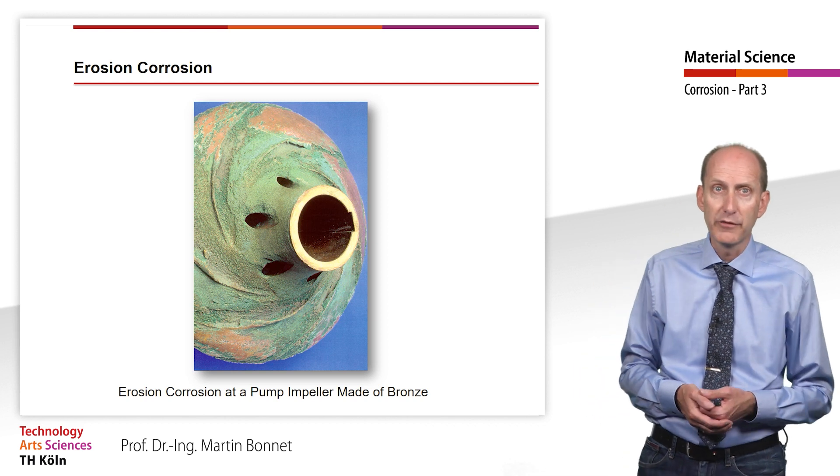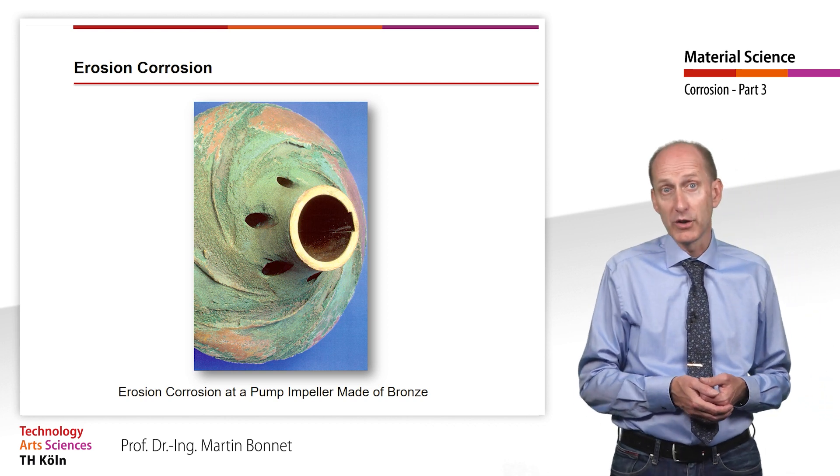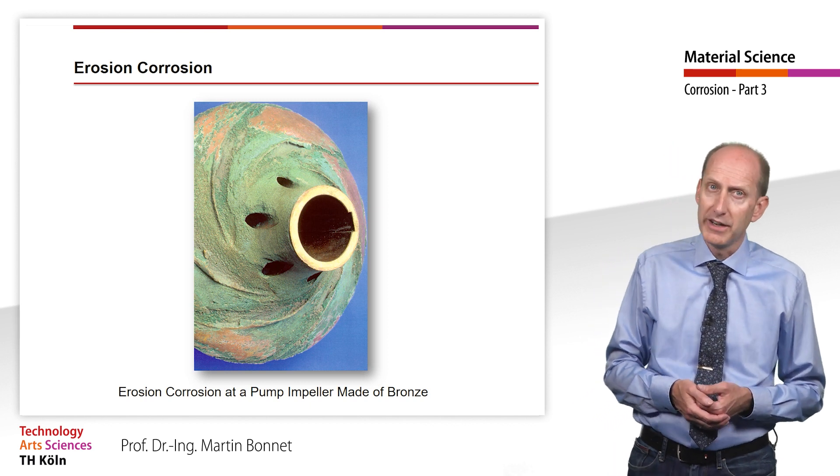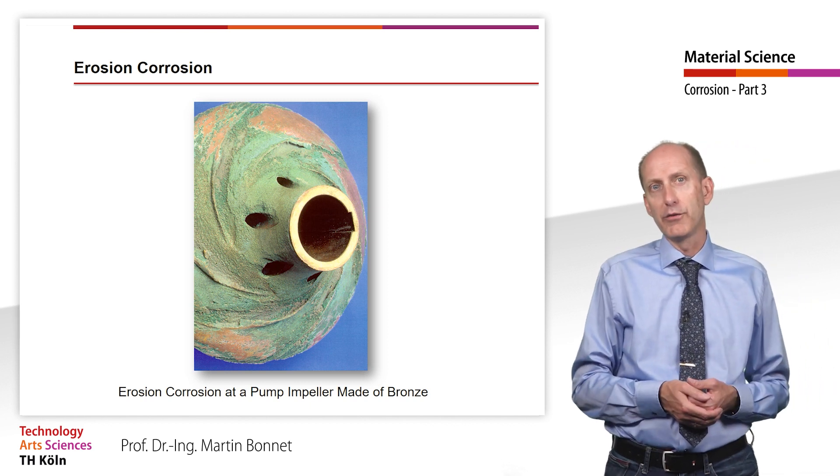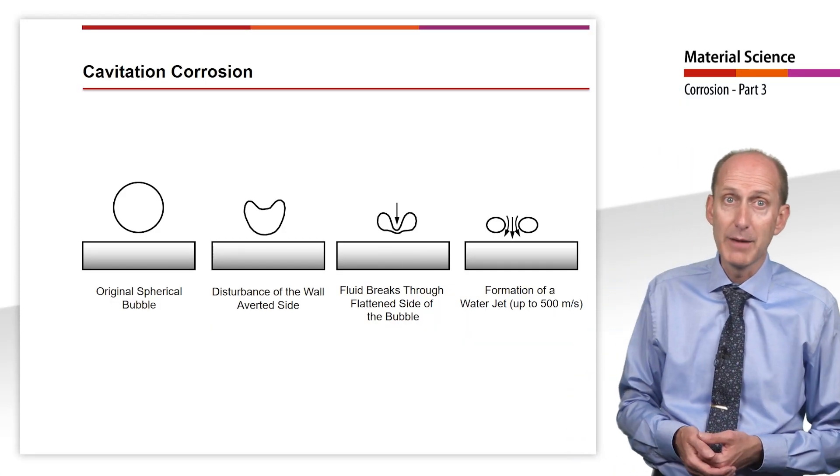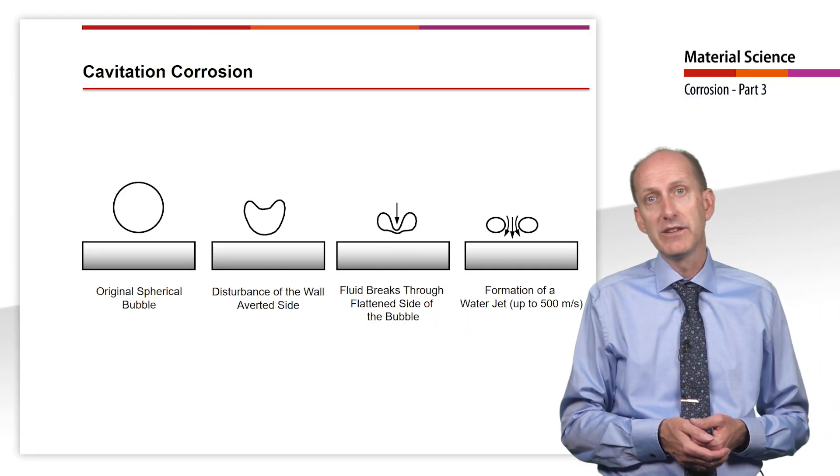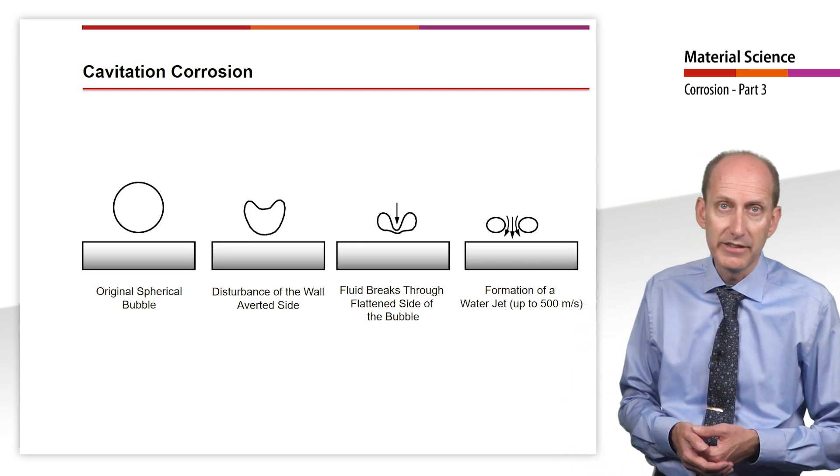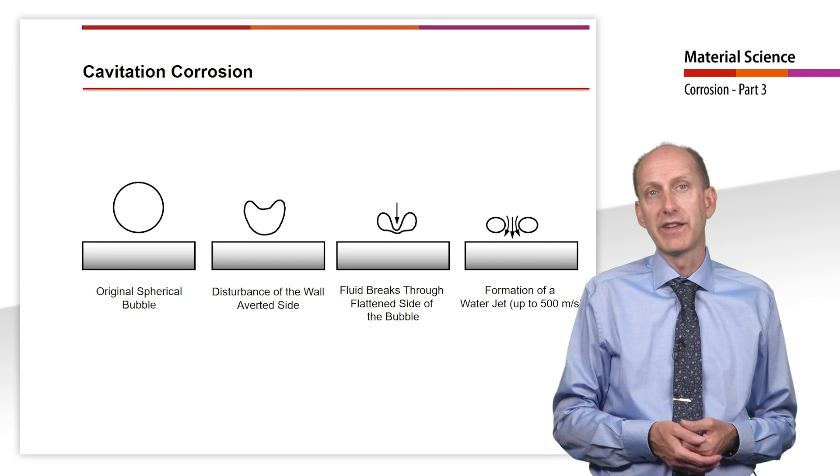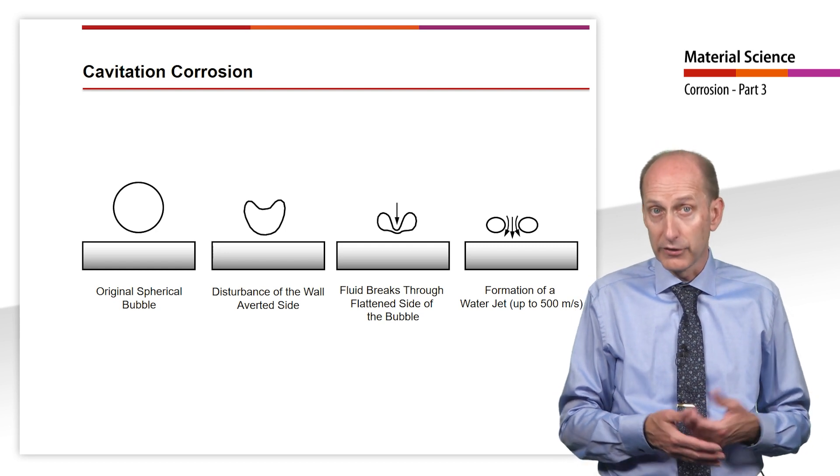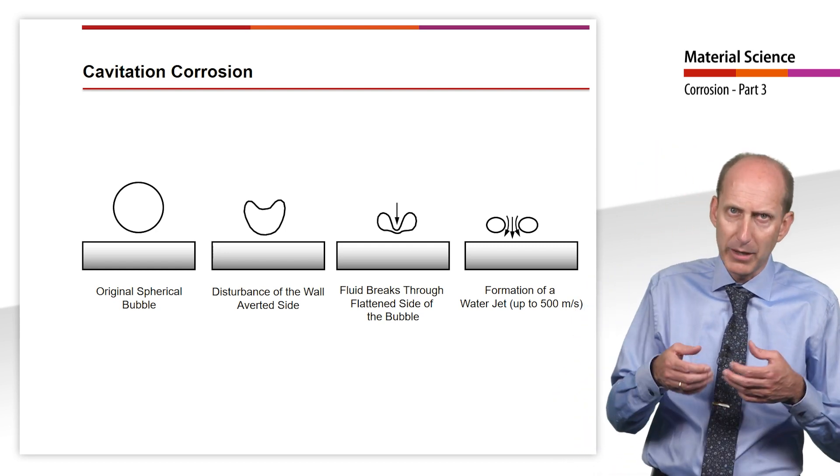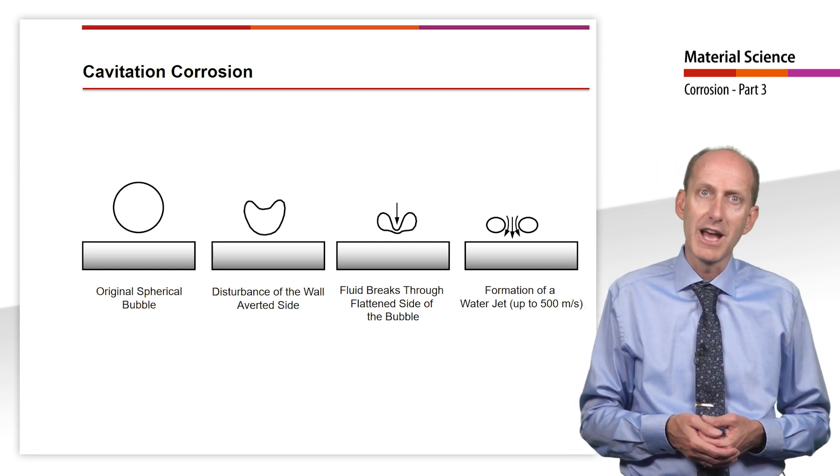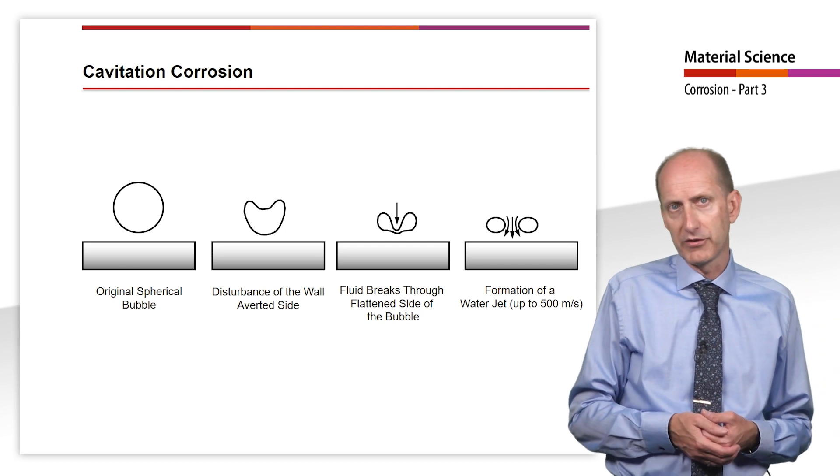In this picture we see an affected pump impeller, which was made of bronze. After a short period of time, there is already very little left of the guide vanes. Another interesting type of flow induced corrosion is cavitation corrosion or cavitation erosion. This can occur in the case of gas bubbles in the medium. Under certain flow conditions, the gas bubbles can implode, resulting in short term local flow velocities up to 500 meter per second.